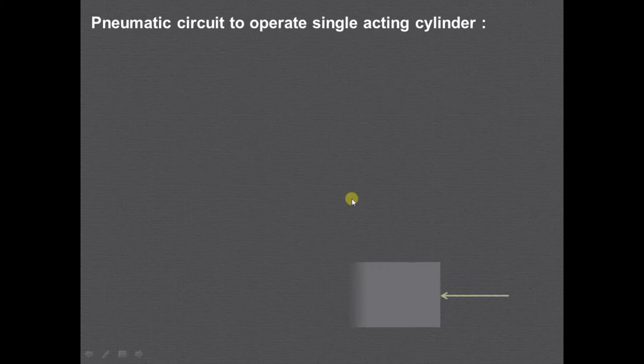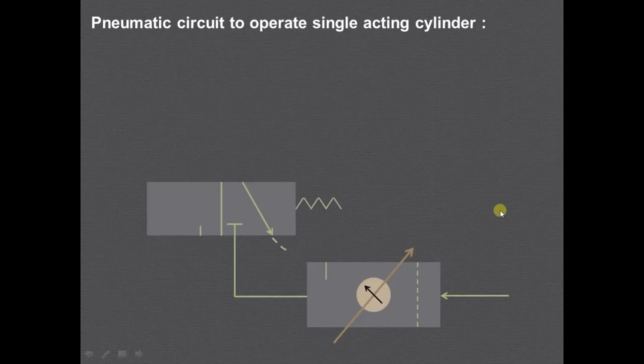Friends, as we have discussed some basics of direction control valve, let us try to understand the circuit working by using a simple animation. So let us draw a simple pneumatic circuit with single acting cylinder. So the compressed air will be allowed to enter into FRL unit. You can see the FRL unit symbol is drawn there. Dotted line indicates the filtration, the arrowhead indicates the regulation, and the small line elements indicate the lubrication. After that, it is a 3/2 direction control valve, and this is connected further to the actuator.